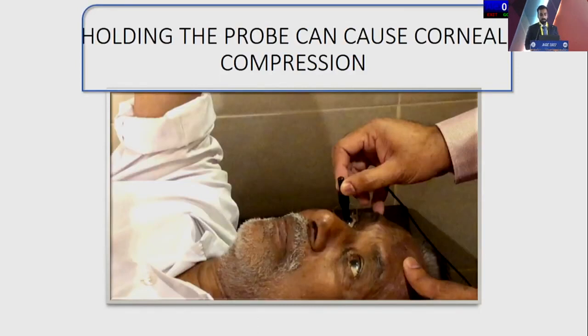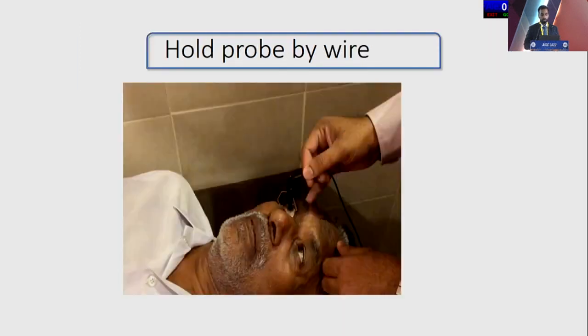Also, here is an example of corneal compression happening, because when you hold the probe with your fingers, you do have a chance of indenting the cornea unknowingly. Whereas if you hold it by the wire, the chances of corneal indentation are greatly reduced, and you get a more accurate axial length measurement with the A-scan.